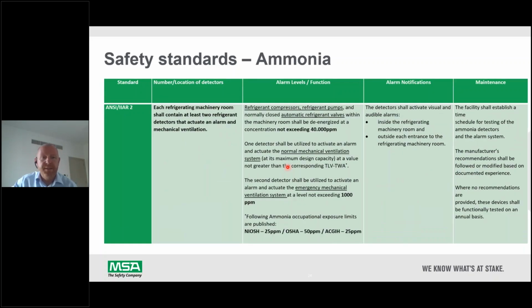And then we have the American standard for ammonia, which is ANSI IIAR2. Again, it's similar. In the plant room, you need to have 2 detectors at different levels. The levels are a little bit higher, but it just says not exceeding 1000 ppm. And then everything needs to be de-energized at 40,000 ppm. The locations of the detectors and the visual and audible alarms are the same as the other standards. So they follow a common theme in the ammonia industry because of how dangerous the gas is.